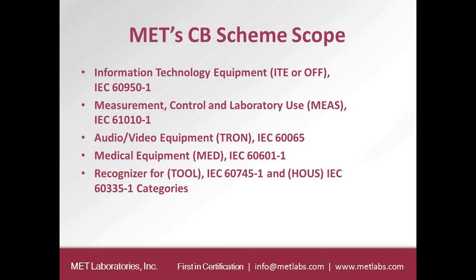Medical, of course, is a big field. IEC 60601-1 is the base standard, again harmonized in the US, Canada, and Europe. There are a lot of different particular standards in medical, depending on the different type of device. There's varying requirements because medical is a very broad field with certain levels of hazards across different pieces of equipment that need to be addressed.